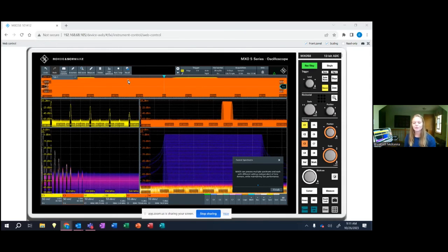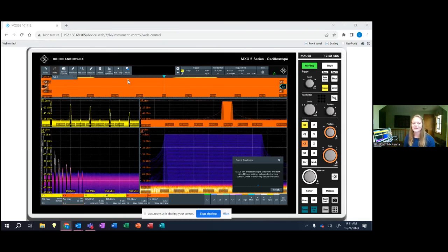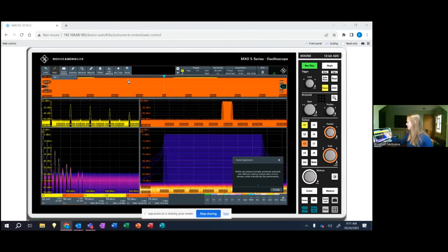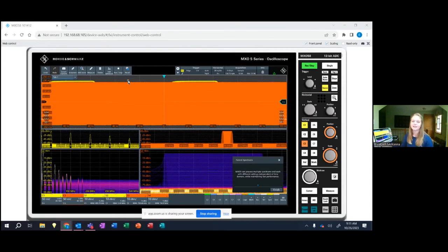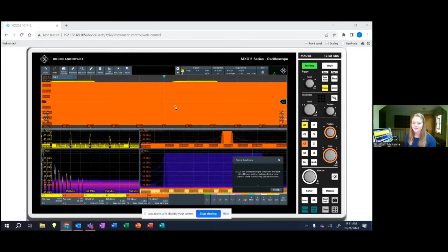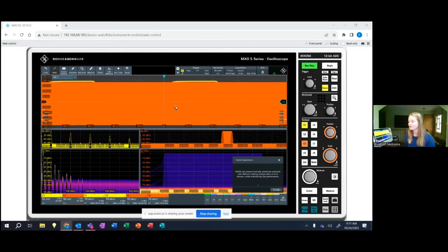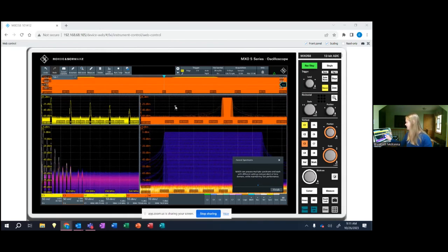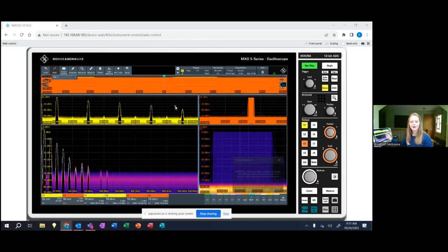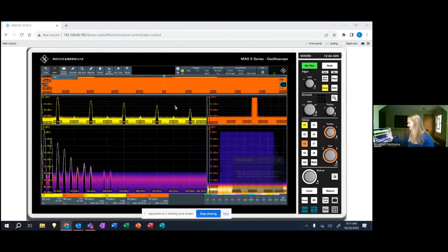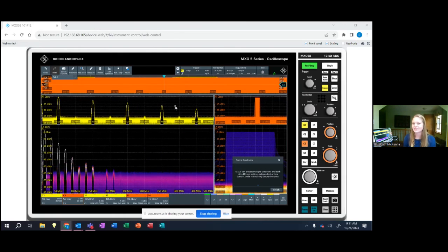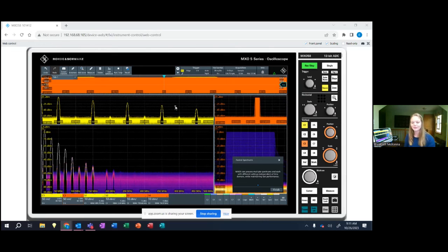Another cool feature with the MXO5 is the spectrum and time domain settings are independent of each other. So say if I wanted to look at the signal in the time domain, but I didn't want to alter the signals in the frequency domain or the settings, I could do so. Really easy just showing you also the cool smart grid capabilities. Say I wanted to look at that a little bit more. Really easy and responsive to be able to use the scope.